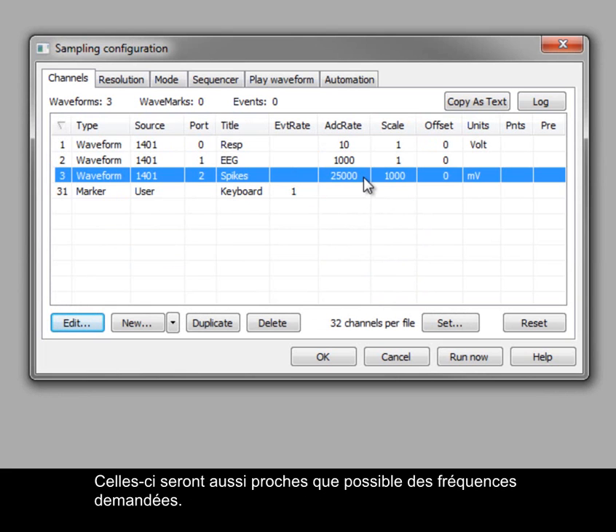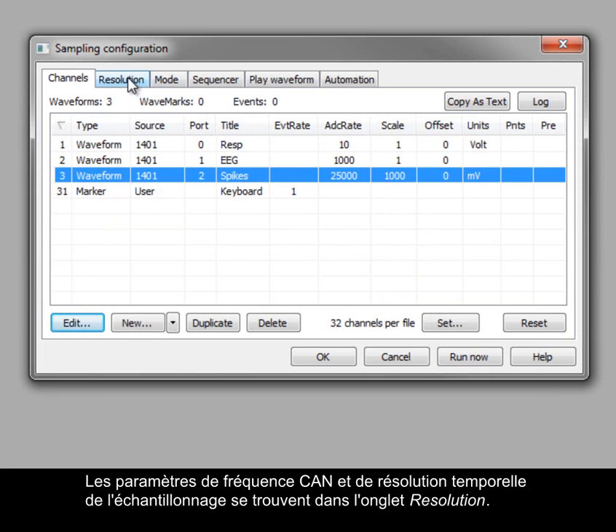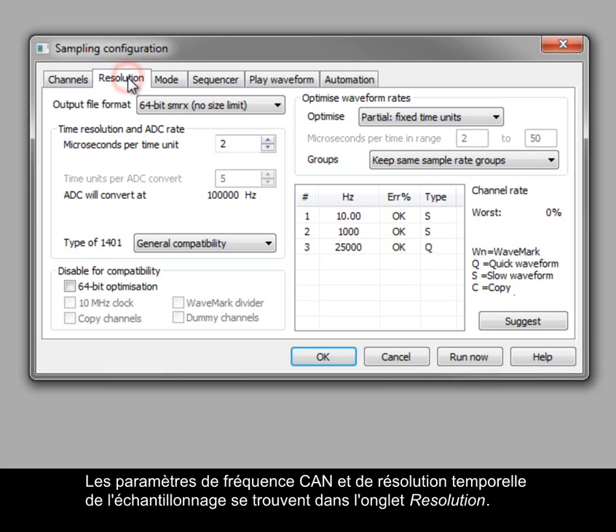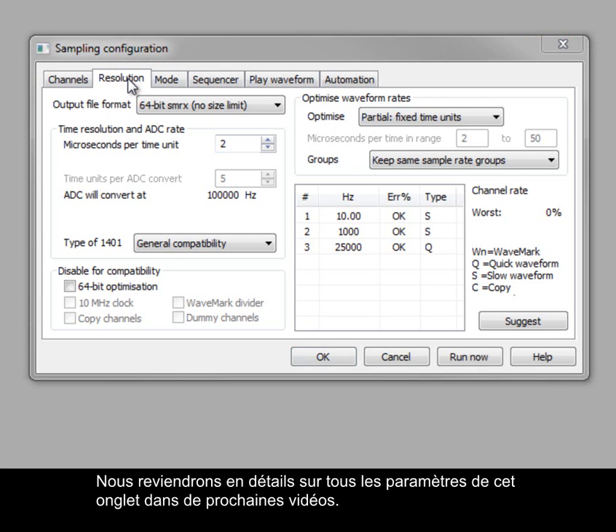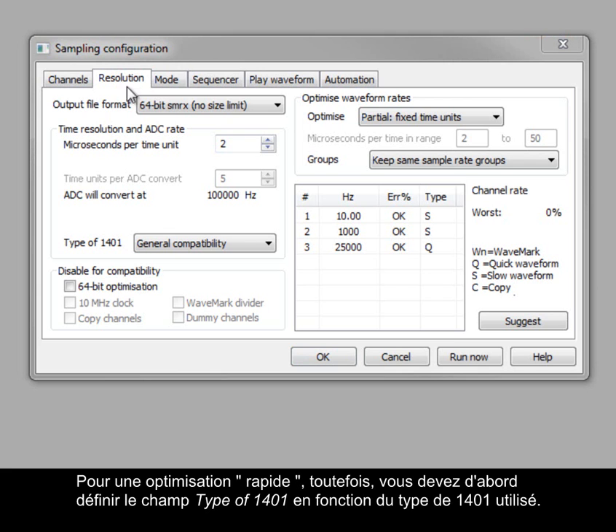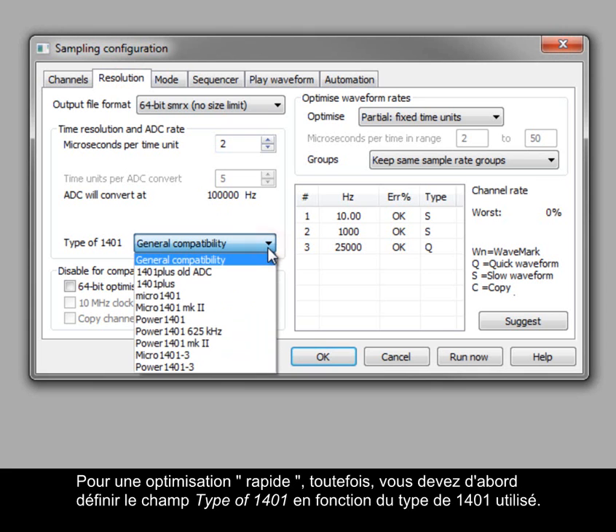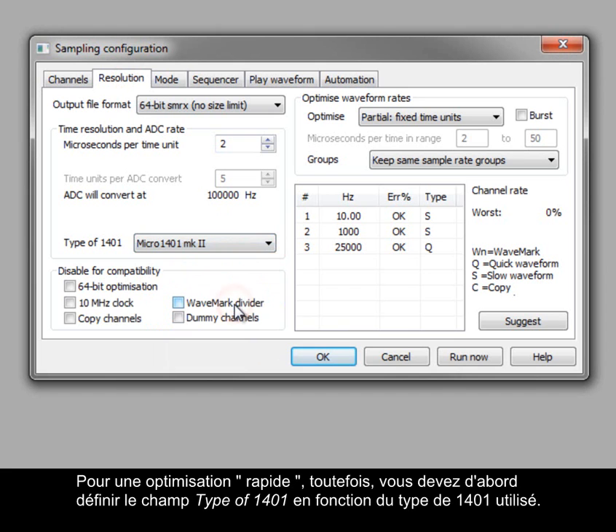The ADC rate field shows the actual sampling rates that Spike2 will use, which will be as close as possible to the requested rates. The ADC rate and time resolution settings for sampling are found in the Resolution tab. We will cover all of the settings in this tab in greater detail in future videos, but for quick start optimization you should first set the type of 1401 field to match the 1401 you are using.